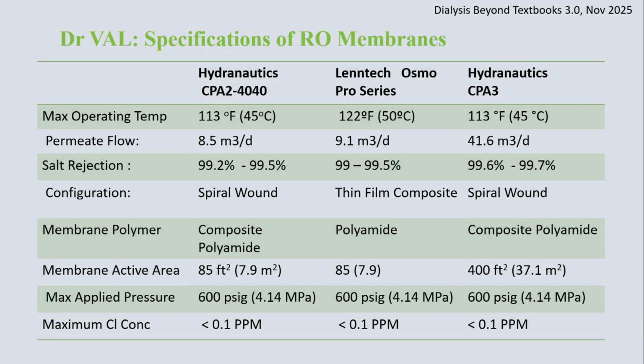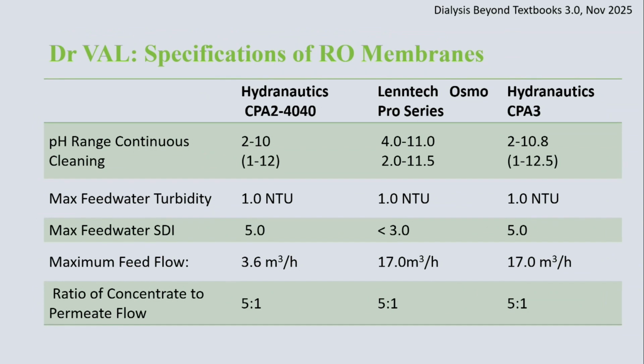The membrane surface area of the Hydranautics and Lenntech is about 85 square feet, and now Hydranautics has come up with what they call the CPA3, which is 400 square feet, which is a much larger membrane, so it has a much higher output. And that is an 80-40 membrane, so it's 8 inches in diameter. Next, yeah. So the pH range at which the RO membranes function, the feed water's turbidity in nephelometric turbidity units. So we've added a turbidity meter pre-RO as well, so that we know that our sand filters have removed enough particulate matter. The silt density index, we could put that in, we don't have it as yet.